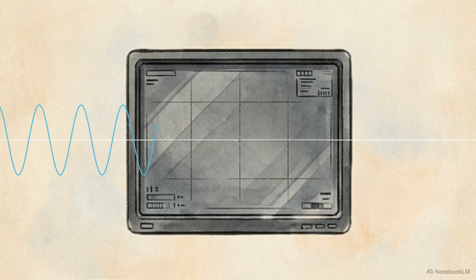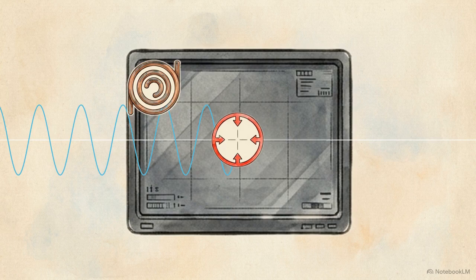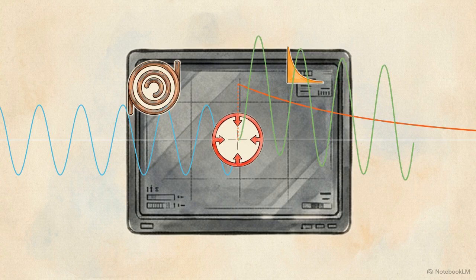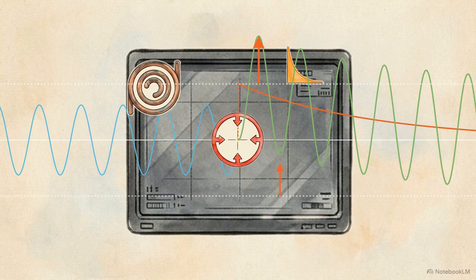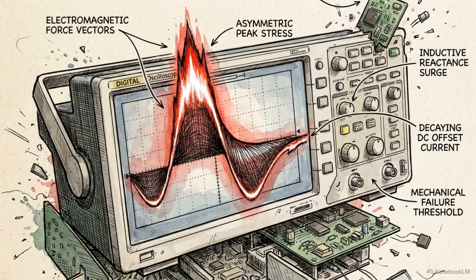At zero voltage, the grid's inductance forces a mathematical correction. Because the physical coils and transformers block the fault current from jumping instantly, the system introduces a decaying surge of one-directional energy, known as an aperiodic, or DC, component. This direct current offset physically pushes the entire alternating sine wave upwards. Instead of oscillating evenly around the center, the massive surge of fault current is lifted completely off its baseline. This distorted off-center wave is an asymmetrical fault.